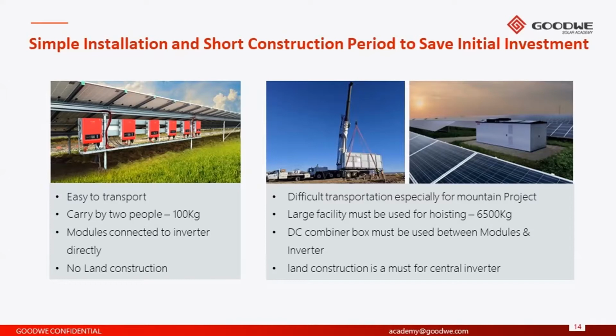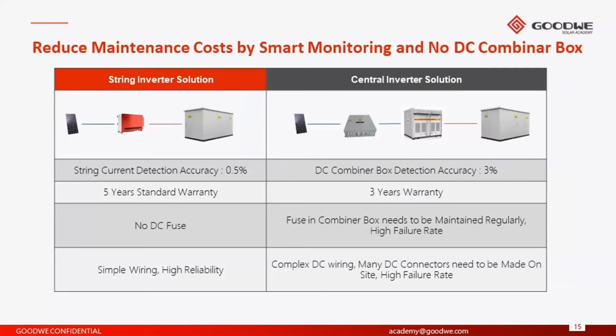And the centralized inverters can weigh up to 6.5 tons. Also, the maintenance cost is reduced by not having to install DC combiner boxes and specialized monitoring inside these DC combiner boxes. We're actually using the MPPT capabilities of the string inverters to detect abnormalities within the performance of each string. DC combiner boxes also come with perhaps a three-year warranty, whereas the inverter itself comes with a 5-year standard warranty, which can be extended to 10, 15 or 20 years.